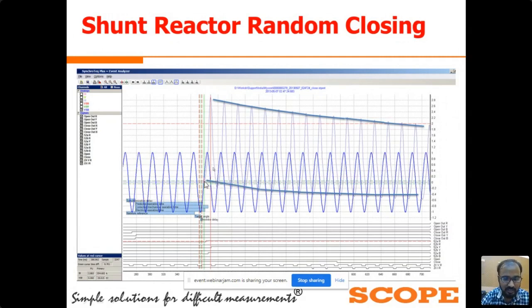So at this point, you can see the current is started at the exact voltage 0 point. So this is the worst moment for the shunt reactor closing. Due to that we have observed here the current started very asymmetrical, and it is near to 3 times the full load current, and the current started to flow in the positive side only.